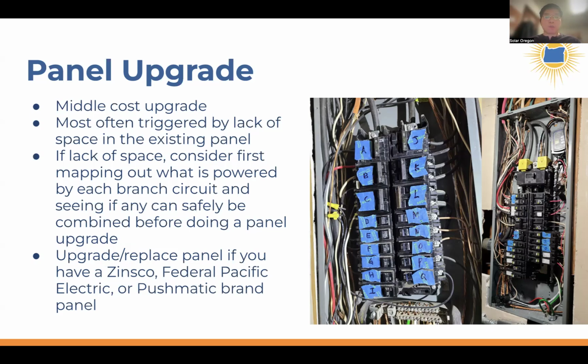If you have a circuit breaker panel from the 1970s, 1980s, or maybe even the 1960s made by companies like Zinsco, Federal Pacific, or Pushmatic, these are panels known to not trip even if you pull too much electricity out of one circuit. They're well known to result in the wire burning up or melting the insulation before tripping the breaker. So many electricians, if they see you have one of these, will automatically say you need a panel upgrade. They won't touch it.